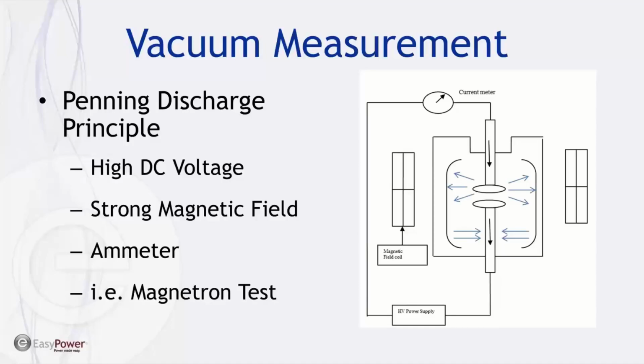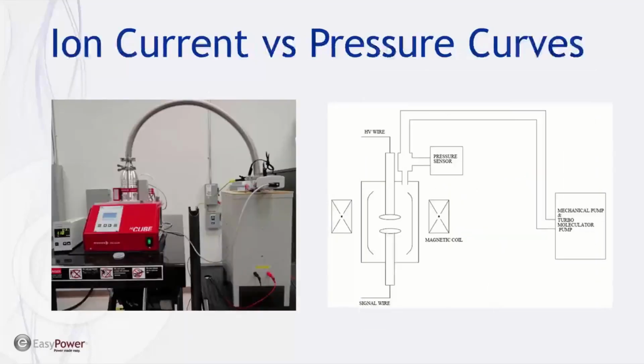Manufacturers of vacuum interrupters call this the magnetron test. They call it the magnetron test because when you couple a high DC voltage with a magnetic field and you trap these charged particles, it in essence becomes a magnetron inside of the vacuum interrupter.